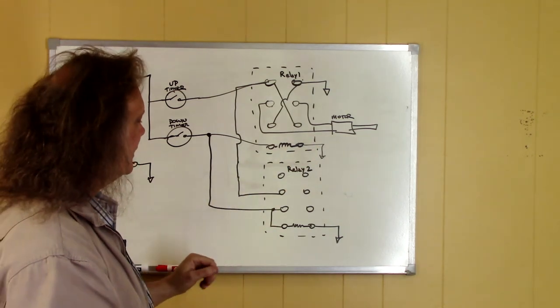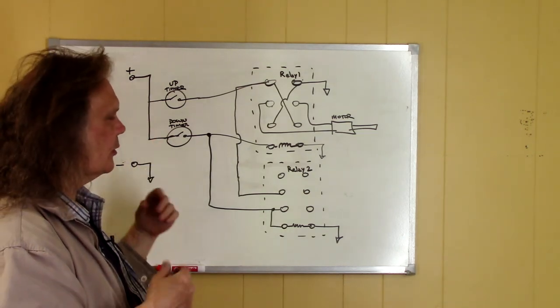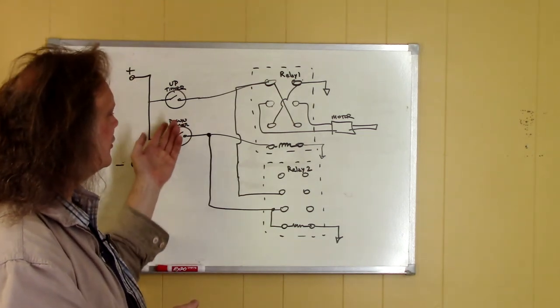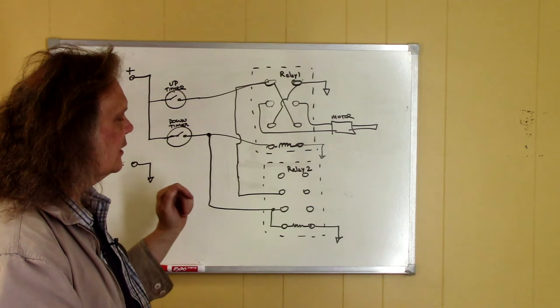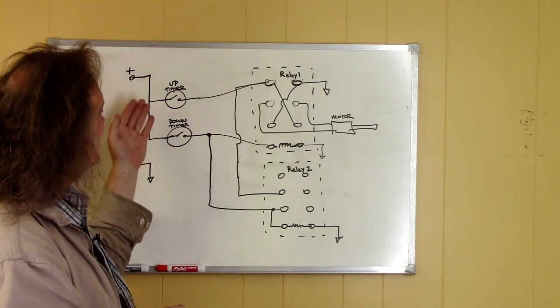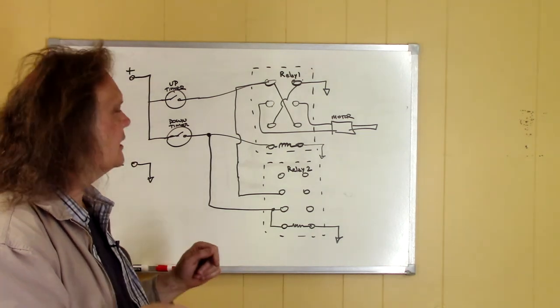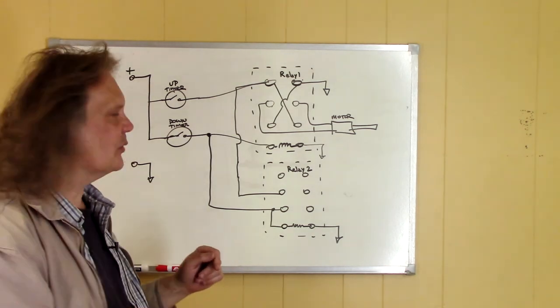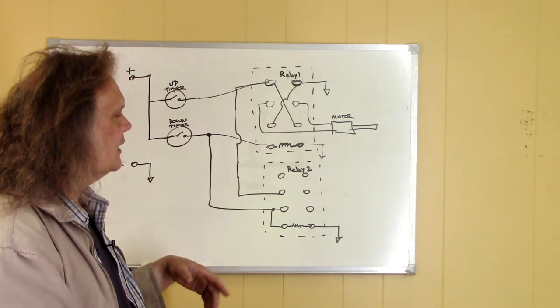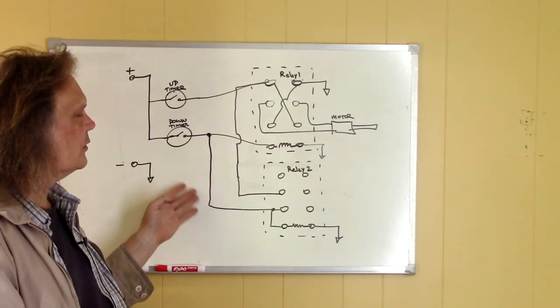So this way we can have a separate timer for up operation and down operation and these timers only actuate for about five minutes which gives plenty of time for the door motor to go through its cycle and after that five minutes they both turn off and there's no power being applied to the motor during the idle periods so this should be a little bit more conservative on your battery because you don't have long periods of time where you're holding a relay down so this is the way you could use two timers and two relays to make it a little bit more sane to program because you just have to worry about the time on one relay versus another rather than the times within a particular event not a big deal either way this one will cost you the cost of an extra timer and an extra relay but in any of these situations any one of these three ways of wiring it up as you can see it's very straightforward and very simple and very convenient.